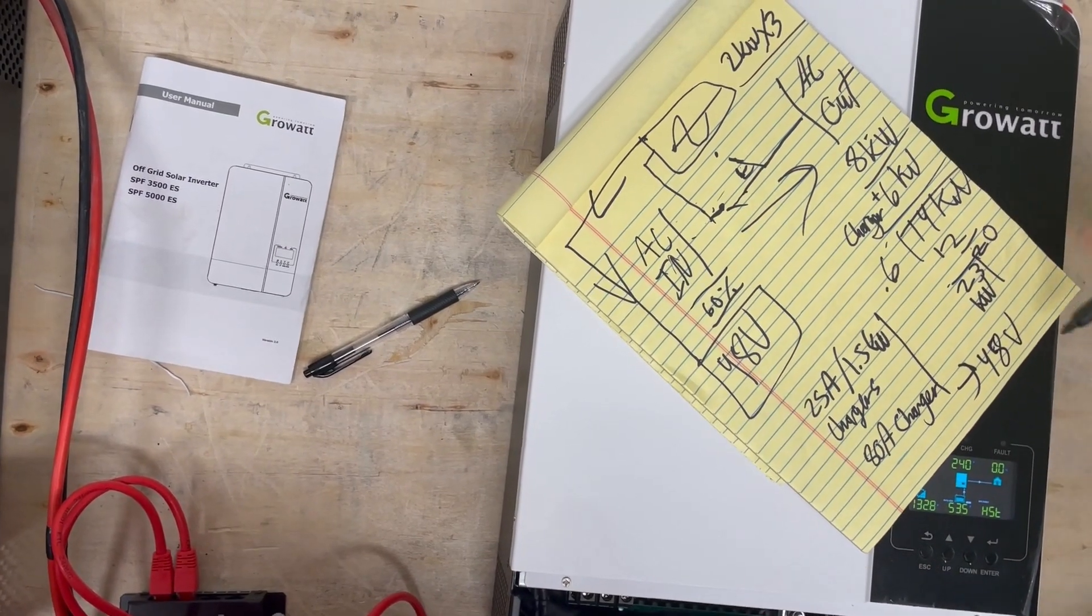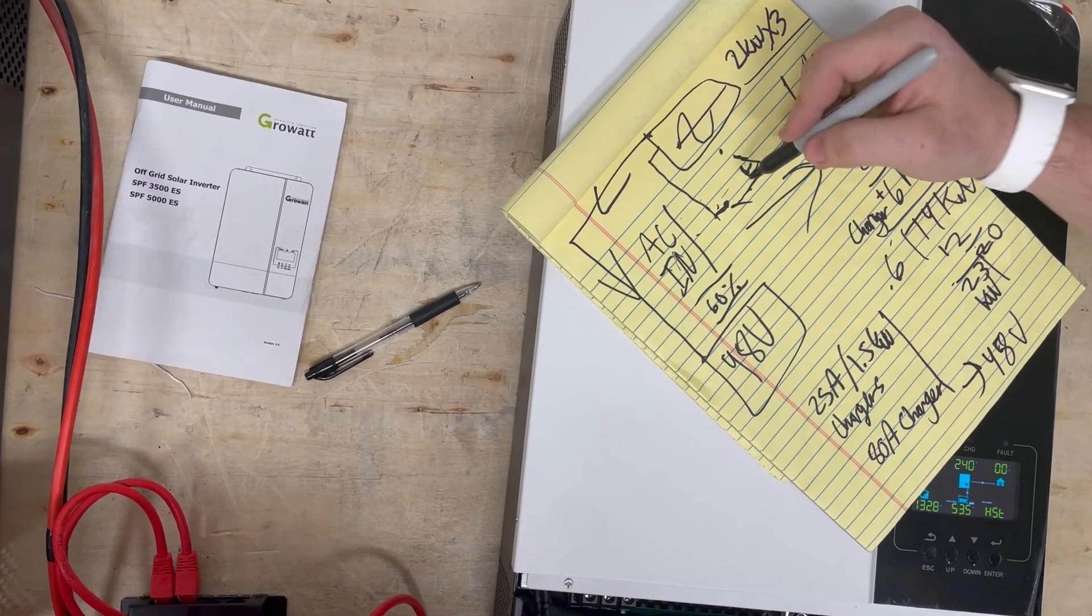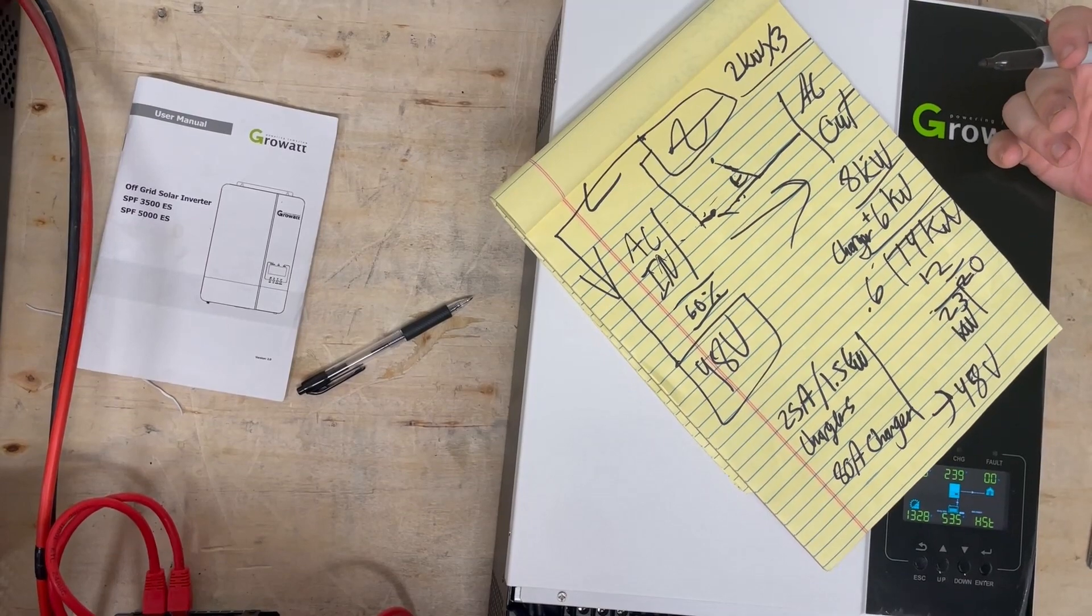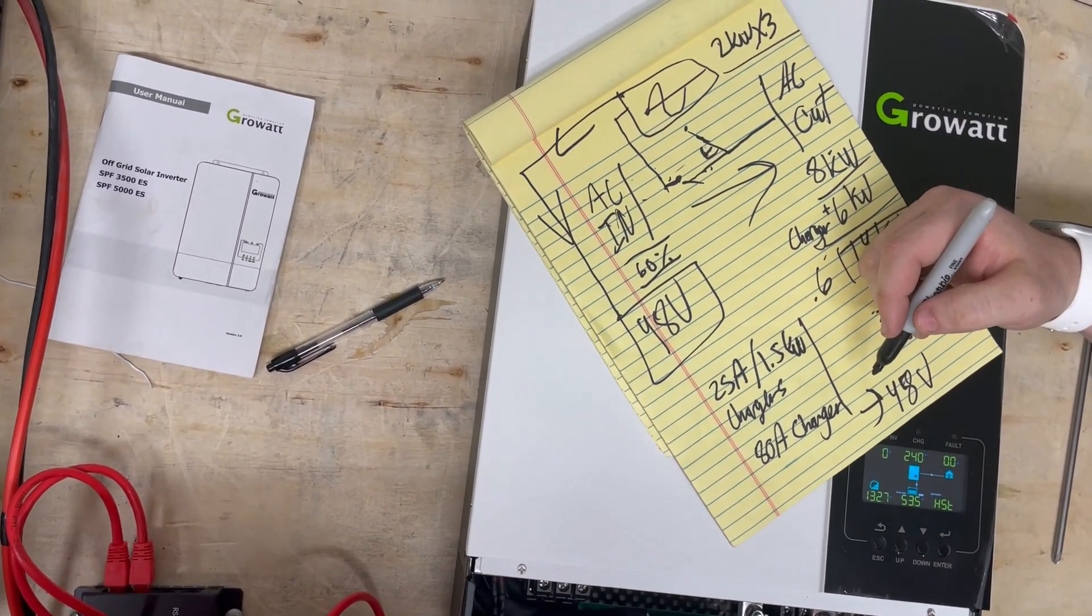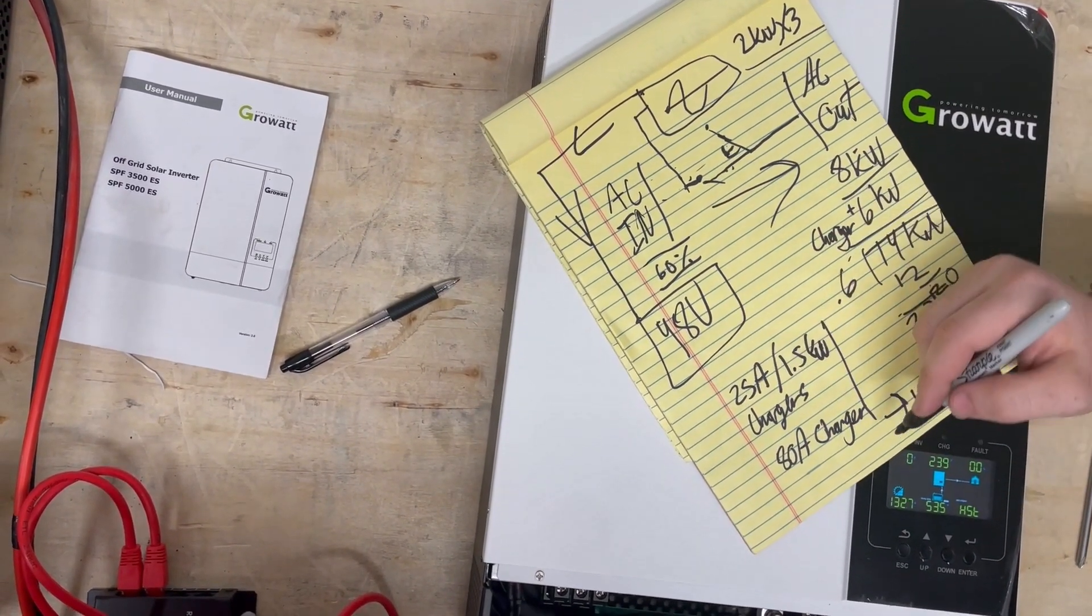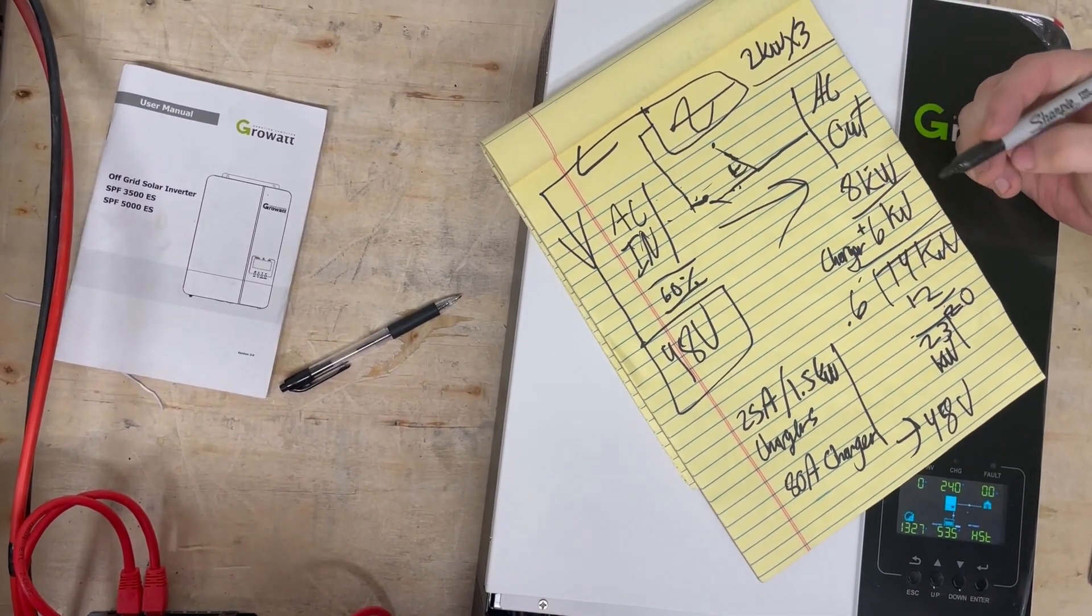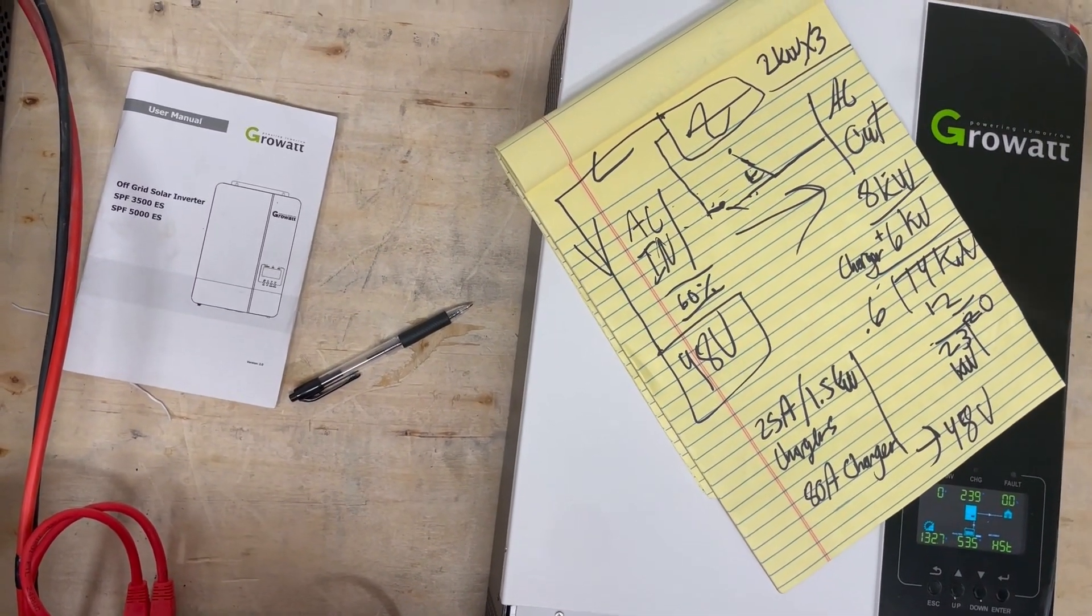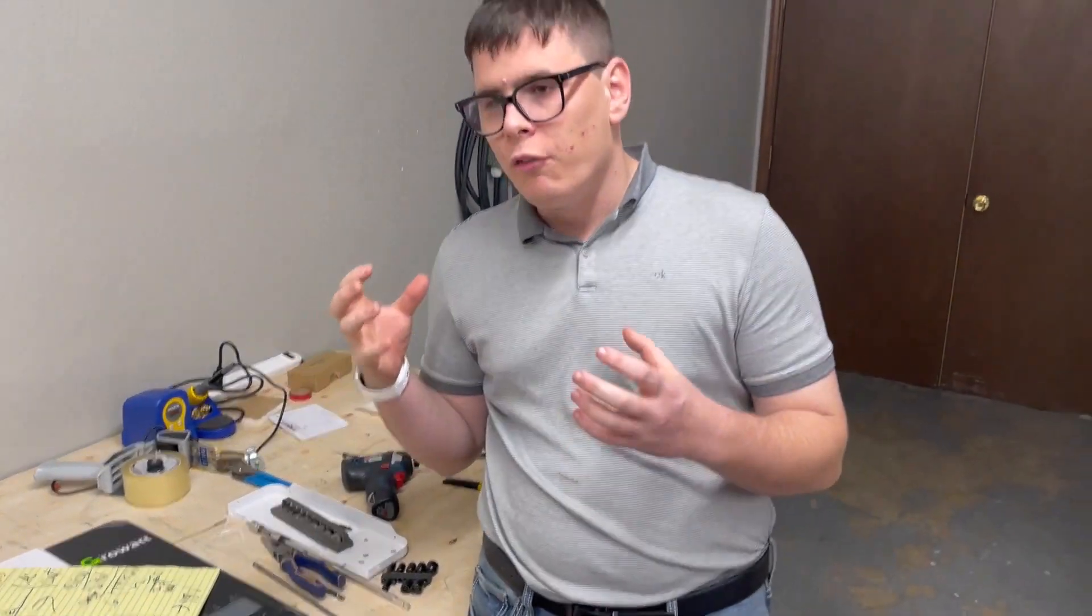The interesting thing that's happening there is you're not disengaging your inverters. This stays connected so your inverters are there to power your loads as they ramp up in the house, but your generator acts as a steady feedstock of DC current charging your batteries. This is the optimal route and it puts the least amount of wear on the inverter, not to mention your home electronics. TVs, refrigerators, computers - they weren't designed to be run by a generator, and you're going to chew into the life of all your appliances.